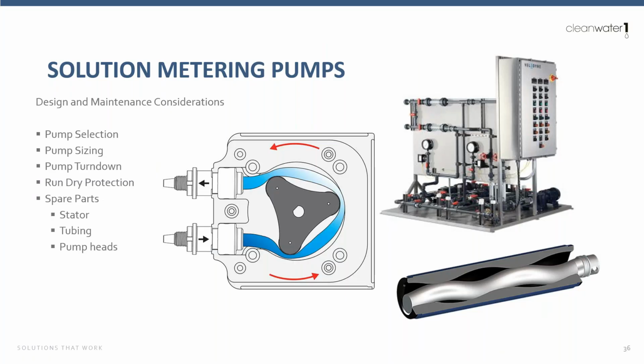For dry systems, solution metering pump, critical part of the process, right? This is what's delivering that properly wetted, properly mixed, properly made down solution to the process. Couple design considerations here. Pump selection, we talked about it. The requirements are a little bit different with dry polymer. Peristaltic pumps may be used a little bit more often, but again, we do generally standardize on progressive cavity pumps.